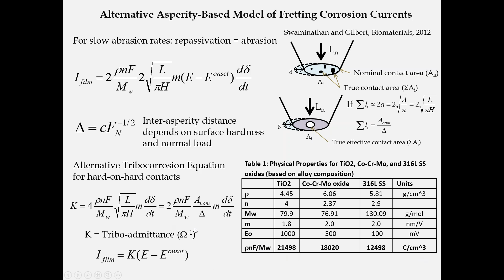So some of the results from our pin-on-disc tests have shown us that there is work done during a pin-on-disc fretting corrosion test where we're sliding back and forth and developing a frictional force over a sliding distance. As you raise the normal force in this pin-on-disc test, the sliding distance gets less because of the compliance of the system. And also, there is an energy dissipated, which is the work or the hysteresis energy within each of these curves, and that varies with the amount of load applied.